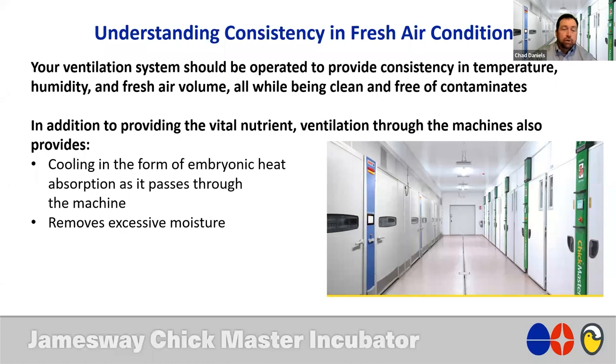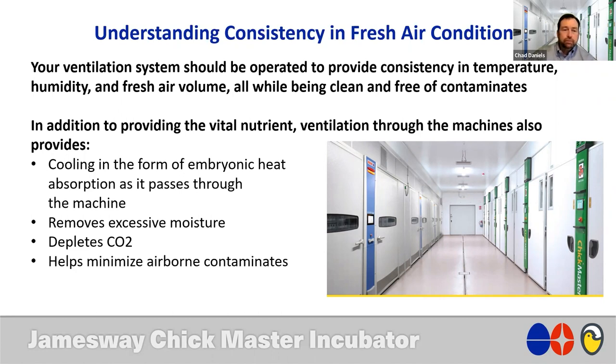In addition, that volume of air removes excessive moisture. That allows us to get rid of all that humidity that we talked about earlier that's produced as the embryos develop. It also depletes CO2. Remember, we can't really remove CO2 out of the air. We essentially deplete it by exchanging air through the machine. And with that air exchange, it helps minimize airborne contaminants.